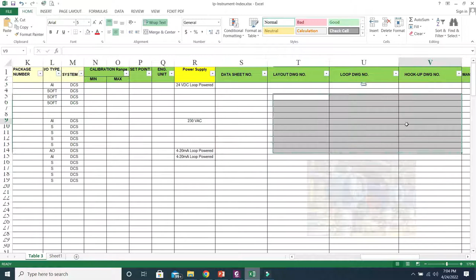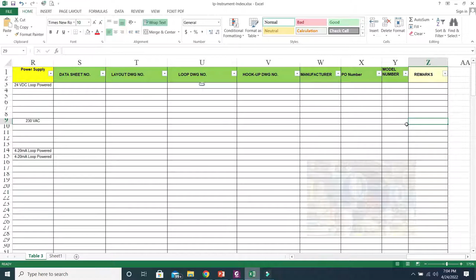And manufacturer name, model number and PO number. In the beginning of the project this information will not be available because we are still doing the engineering, the manufacturer is not finalized, the PO is not placed and the model number is not fixed. But whenever this information becomes available, then time by time we will update the instrument index accordingly. And if anything is not mentioned in these columns and it is important to specify, then we can mention this information in the remark column. So in this way you can see these are the fields we need to update. One by one we will go through each and every P&ID and update all the information. Information which is not available at this stage, we can update after some time or whenever it becomes available.